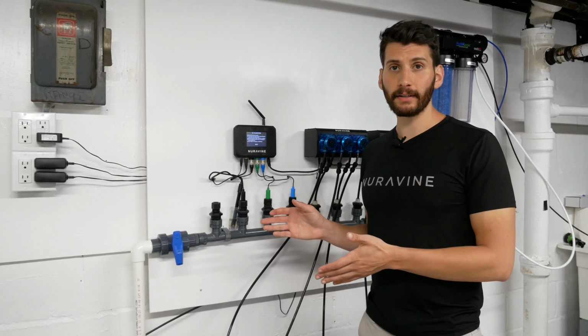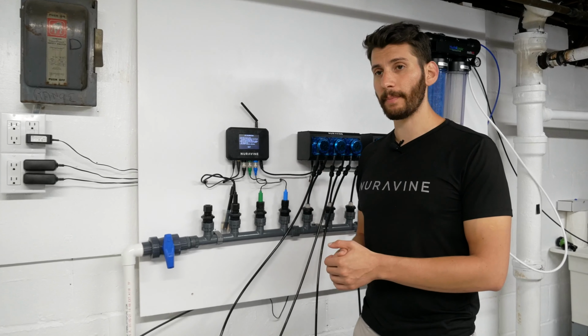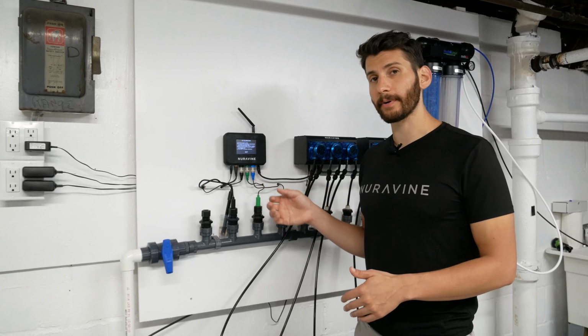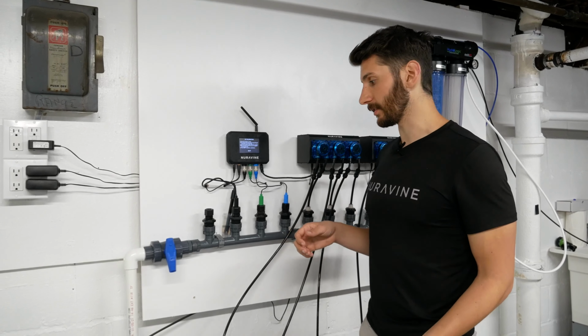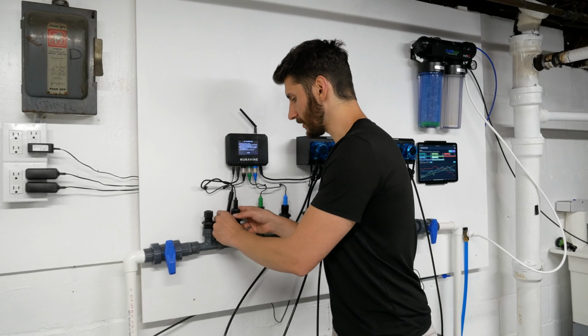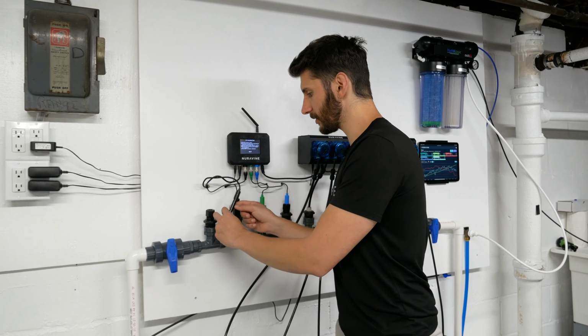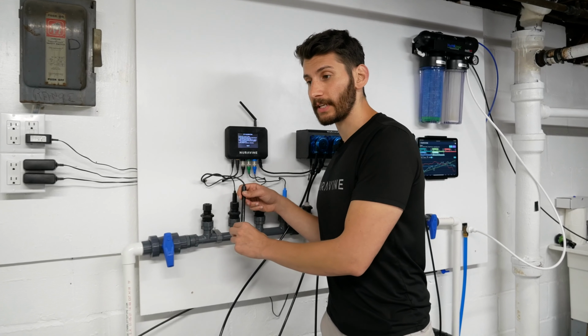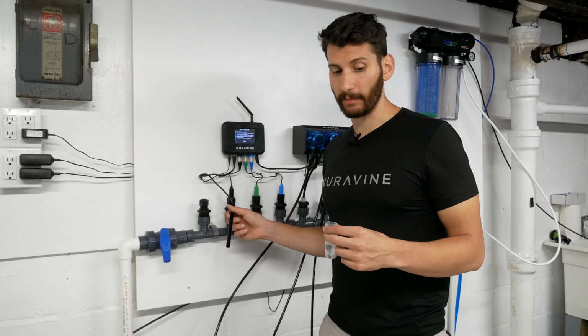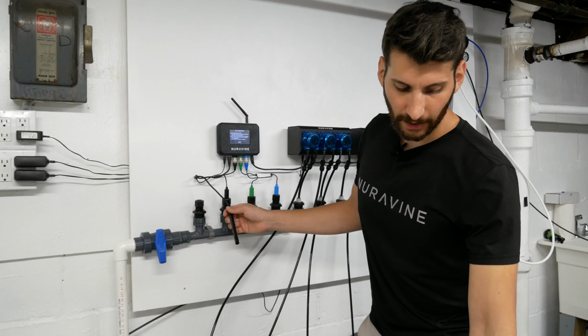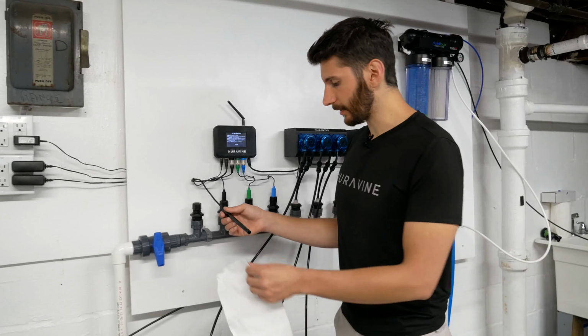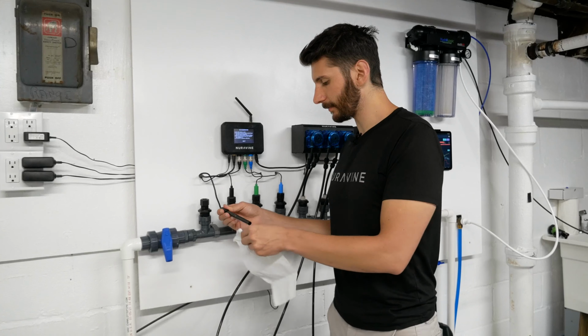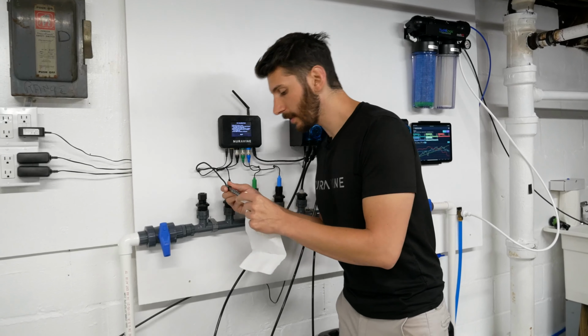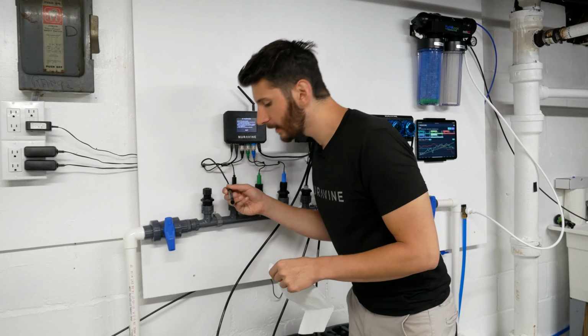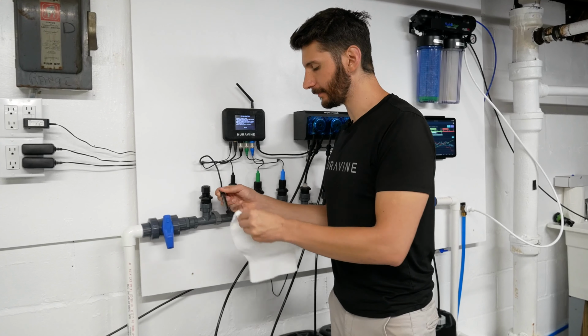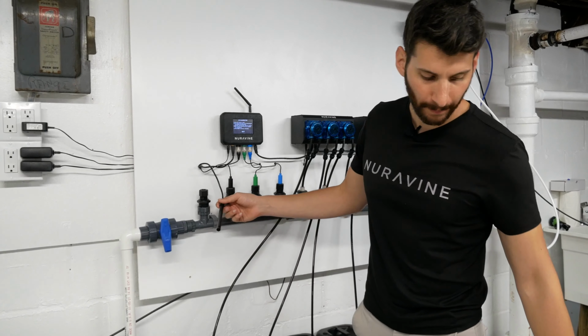Once that's done, this next menu is going to show up and it's going to tell us to clean off the probe and put it into the high calibration solution. So I'm going to take the probe out of this solution, and I'm not going to throw this away just yet because I like to use it at the end to confirm my calibration. So I'm going to set it off to the side, and again I'm going to wipe down my probe with a cloth. I'm going to blow to get everything out, wipe it down again so it's nice and dry.